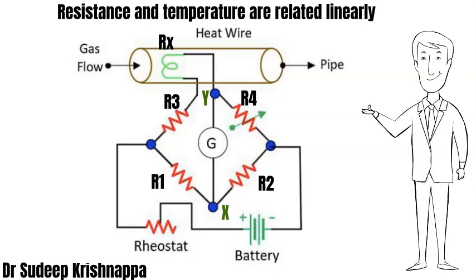When the bridge is balanced by altering R4 depending on the resistance of Rx, and gases flow over the heating element, they take away some of the heat, resulting in a drop in temperature. This alters Rx, changing the total resistance at position R3 and unbalancing the bridge. By altering R4, we can balance the bridge back again. The degree of alteration in R4 gives us the degree of change in resistance at Rx, which is linearly related to temperature, allowing us to measure the flow of gases.